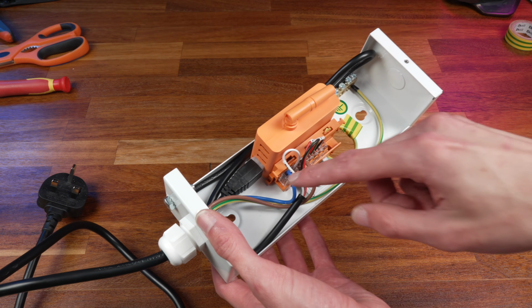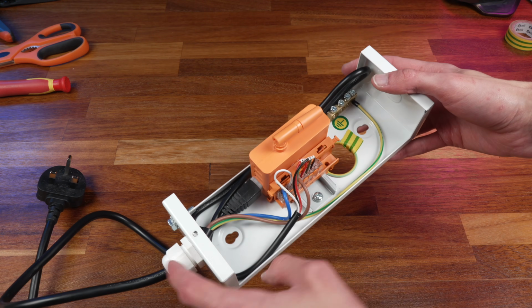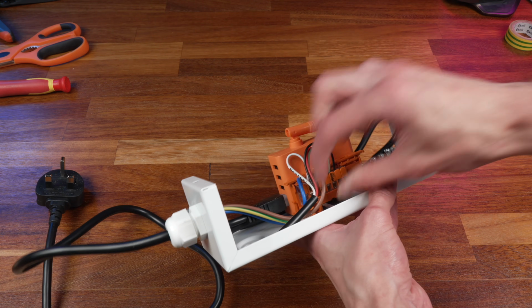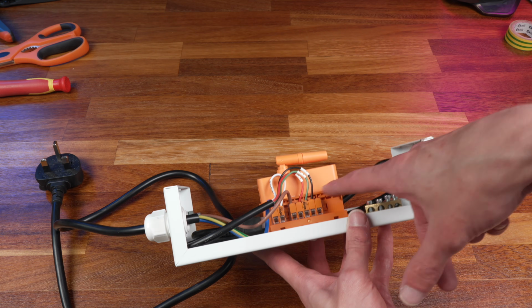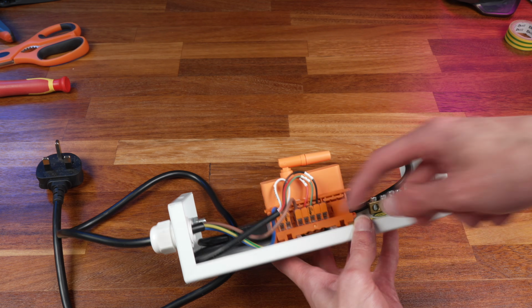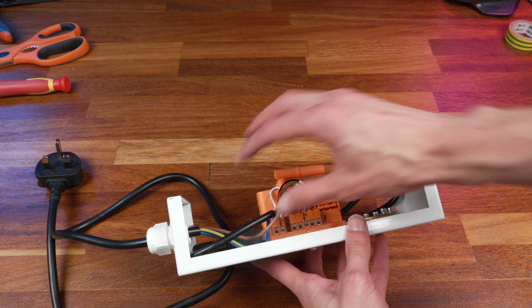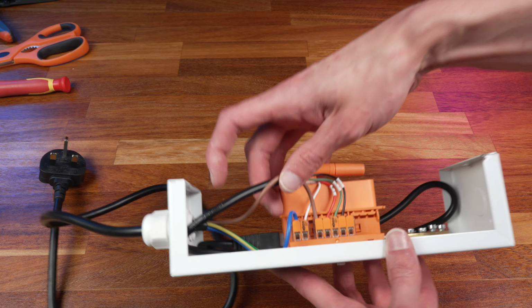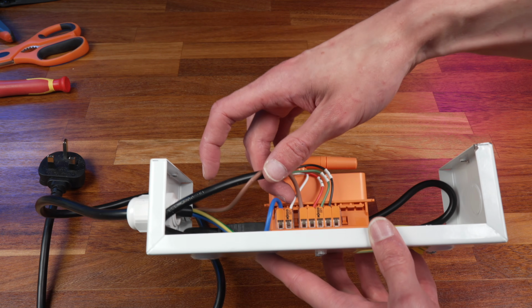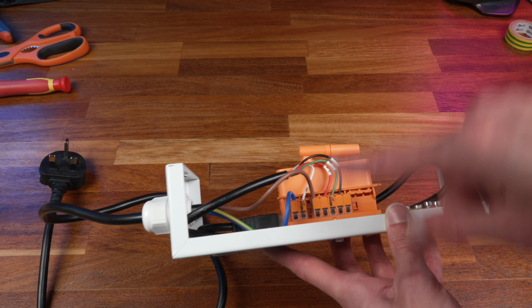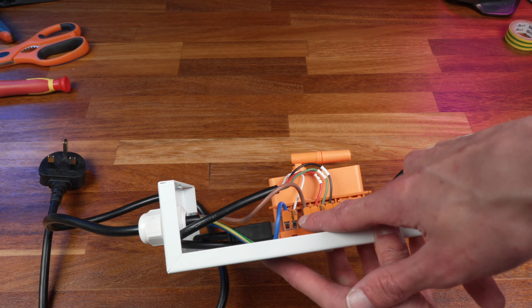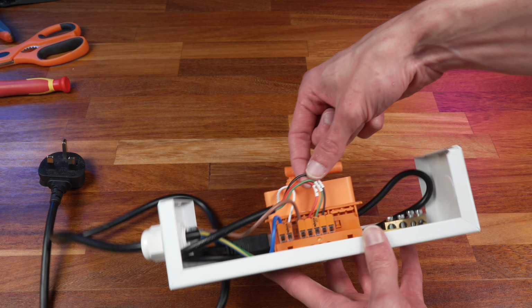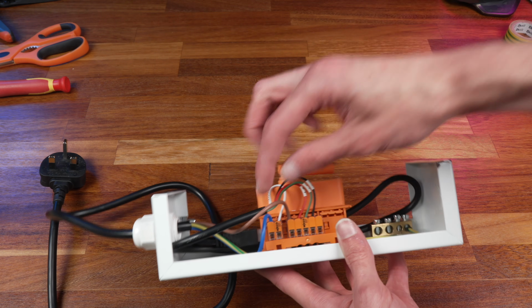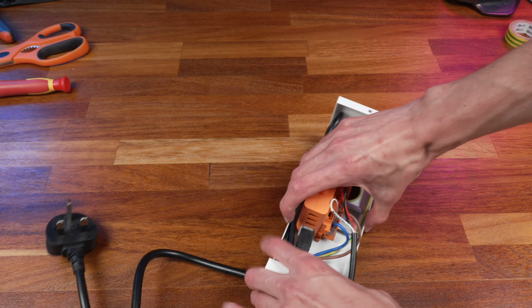And then I've brought those all around it here. The line and neutral that come in go into these two Wago terminals. It's a really neat little Wago 221 DIN rail carrier. I've got a bunch of these, they're actually really nice. So that mounts on the DIN rail there. I have a pair of Wago 221s, one here for the neutrals. The neutral comes into that and then comes out onto the fly lead, onto the neutral there. And then the line comes in from the flex into here, and then the three different lines, A, B and C, go off to the energy monitor. So that's now all installed there and ready to go.